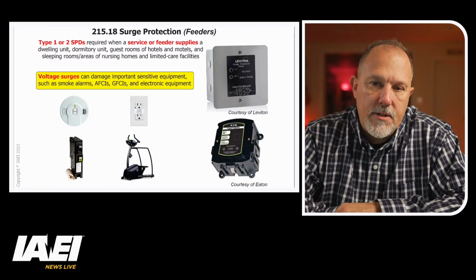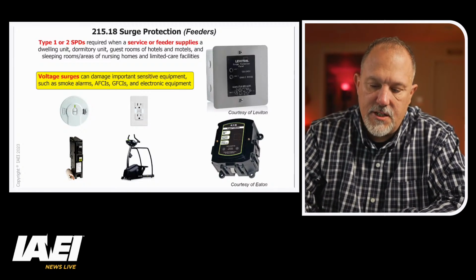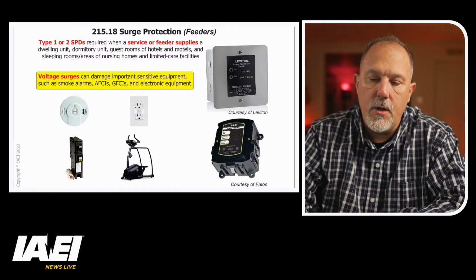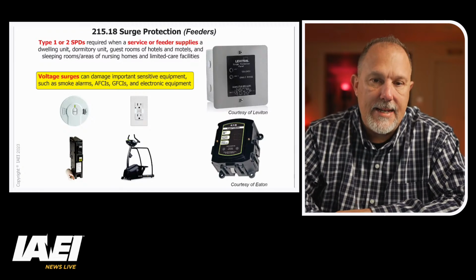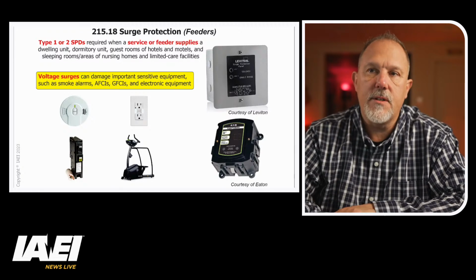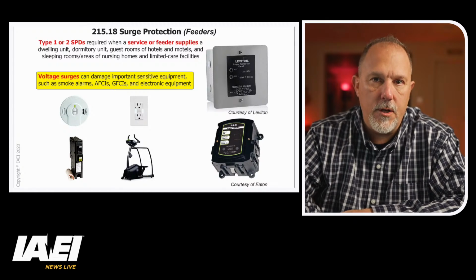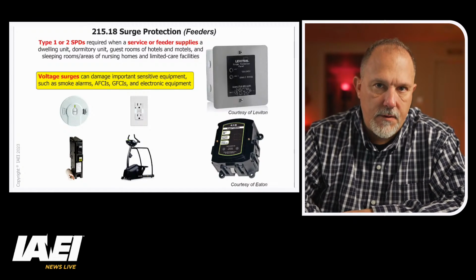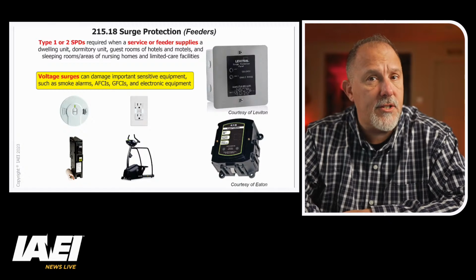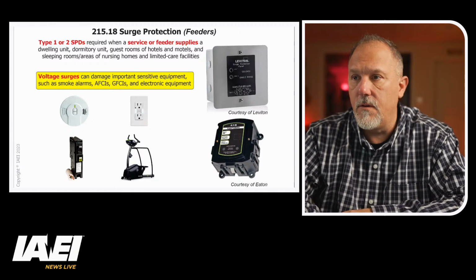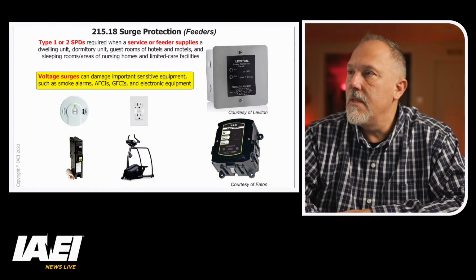So a Type 1 or Type 2 SPD is permitted, and that's in 215.18(C). You can have a Type 1 or Type 2. A Type 1 can be placed on the line or load side of the service overcurrent device. A Type 2 can only be placed on the load side of the service overcurrent device.